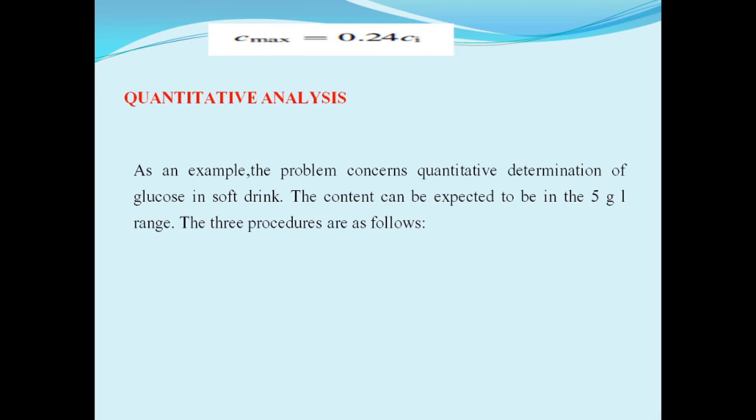It is necessary to do a new calibration for each set of quantitative analysis. If older data are used, it is quite possible that the actual chromatographic conditions are slightly different, which may give rise to systematic deviations. Since quantitative analysis can be based on either peak area or peak height, the term signal means both possibilities.